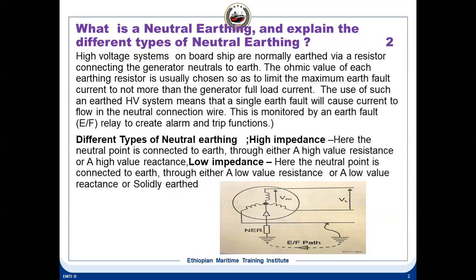So how can you get rid of this? An isolation transformer can be placed. Some of the tanker ships in the hazardous area don't use these neutral earth systems. So there they have a separate isolation transformer, and they take the power from that.